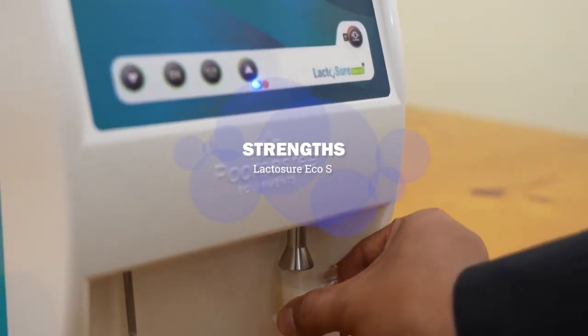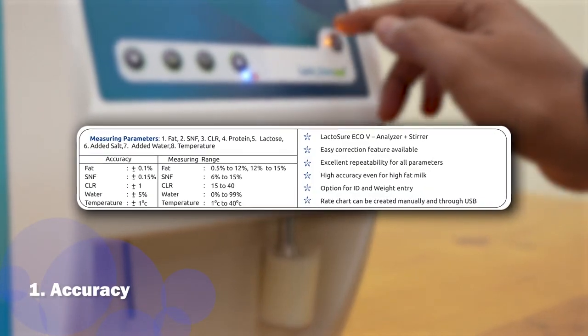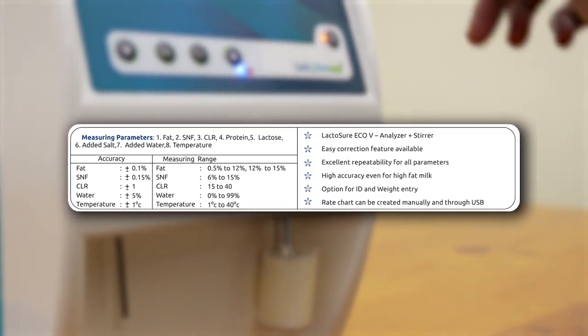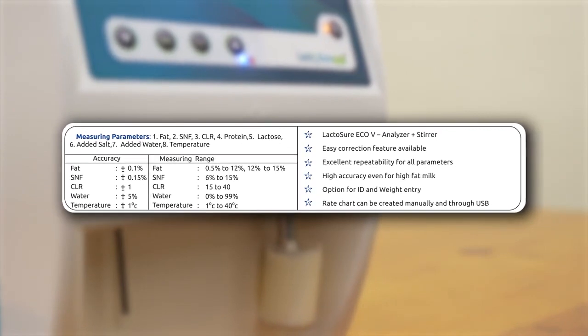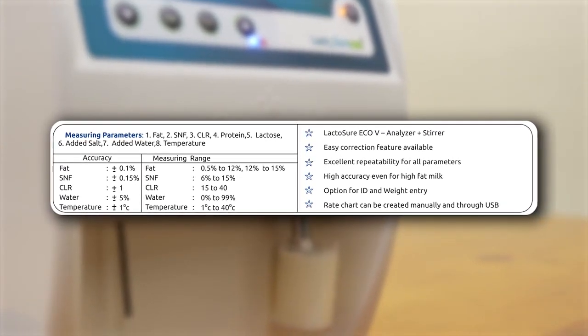Strengths of LactoSure Eco V: it has an accuracy of plus or minus 0.1 for fat and plus or minus 0.15 for SNF, even for high fat milk, with a wide range of 0.5 to 14 fat sample.